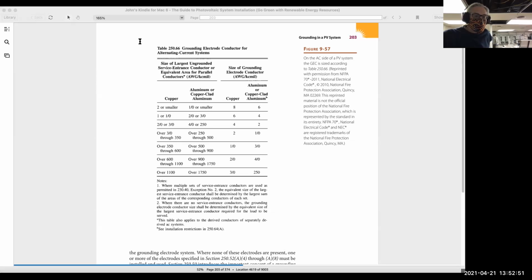Let's try Menards just to see if it pops up. I like to show places that you guys can go to, so if you get inspired, you can literally go on a trip over to Menards and take a look at this, physically touch it with your hand and go, okay, that's a grounding electrode. So we would buy that. You need a truck with an 8-foot bed or a van because it's going to stick out the back. You're going to take that back to your job site, and out there by your solar system, we're going to drive that into the ground because we're going to take our green wire and connect to it with what we call a football clamp.